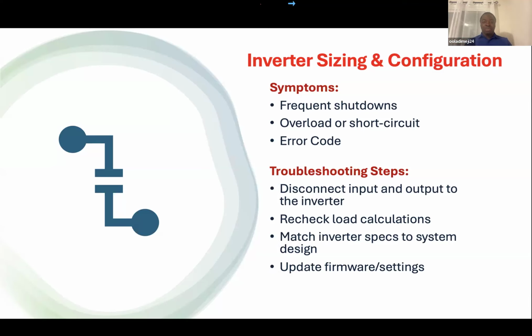So that's part of the troubleshooting steps you do. Then you recheck your load calculation if you are having overload. What have I recommended? Based on the load, what are the loads that are supposed to be connected to the inverter? Then you match the inverter specification to the system design. Sometimes also, if the firmware or the settings of the inverter are not well done or are outdated, that can cause systems to shut down intermittently. So sometimes all you need is to update the firmware of your inverter.